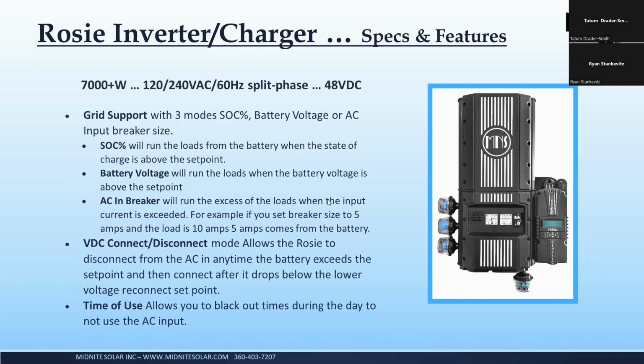So if you put it in SOC or battery voltage grid support, what that will do is, let's say you set it for battery voltage and you tell it at 54 volts, I want you to power the loads. At 54 volts, the Rosie will start supporting the loads with battery power to maintain 54 volts. So you may have, say, 1,000 watts of solar and 2,000 watts of load. It would draw 1,000 watts from the battery or from the solar, and it would draw 1,000 watts from the grid. And it can vary that based on what you have available. So that's a really nice kind of grid last type thing, or grid zero, you may want to say. And that can run on state of charge or battery voltage.